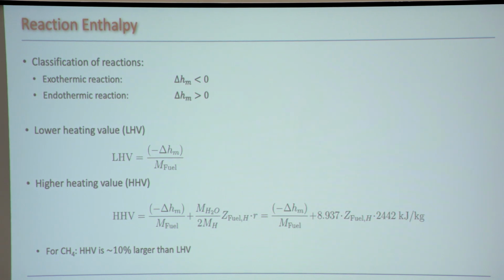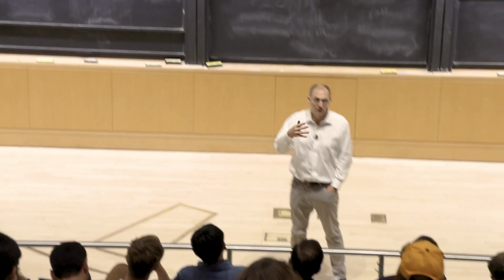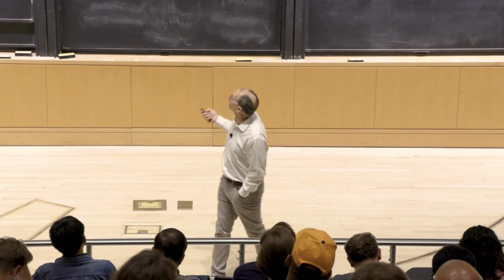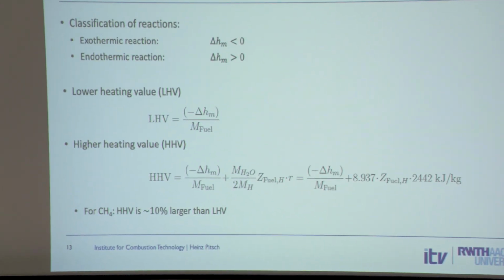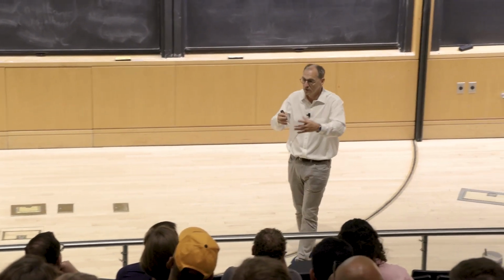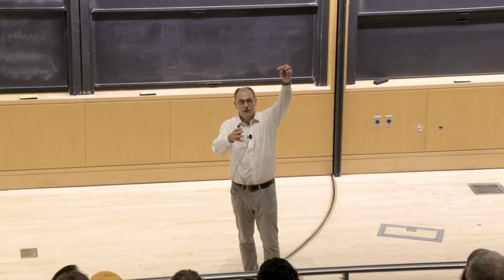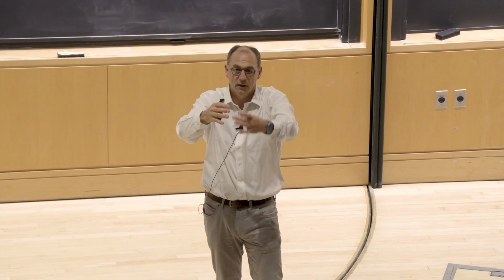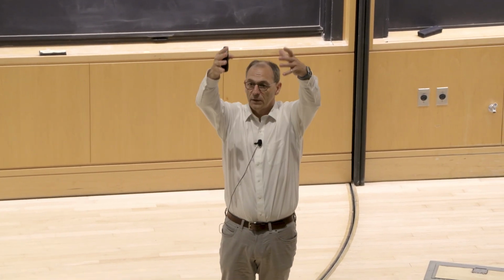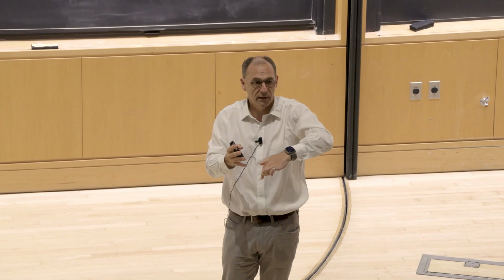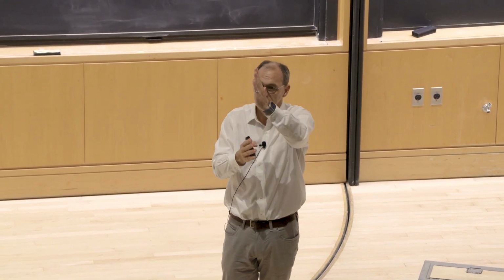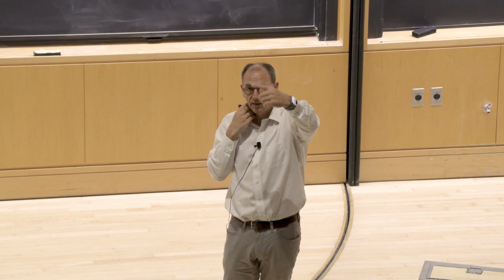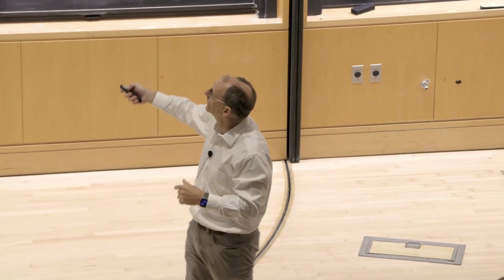And if you take domestic heaters, they are built to use the upper heating value, the higher heating value, by condensing the water. So you have the exhaust that goes out, and fresh air coming in, in a kind of heat exchanger fashion. You have a chimney with a concentric outer pipe where the air is drawn in and the exhaust goes out, and while the exhaust is cooled down, you heat up the air, but then the water condenses and is extracted.